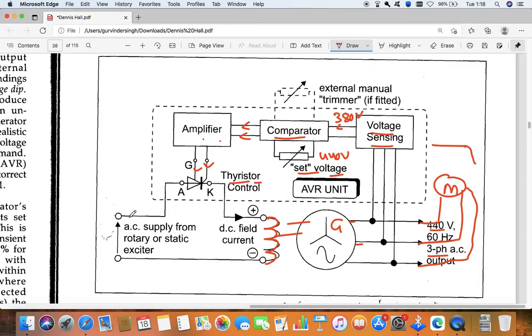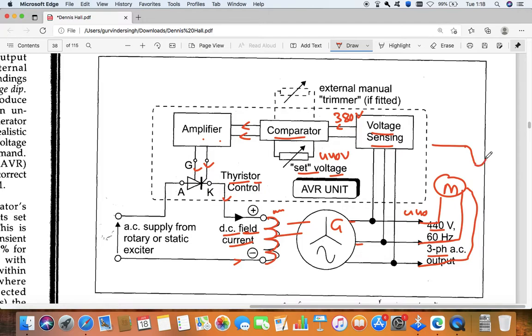The thyristor - we are applying AC supply to it, and it will convert it into DC also and control the supply. That signal from the amplifier will activate the thyristor, and it will increase the supply to the field coil. When it increases the supply, it increases the DC field current, and that DC field current will cause the voltage to increase. So the voltage increases back to 440. Due to some lag, it will increase a little bit more.